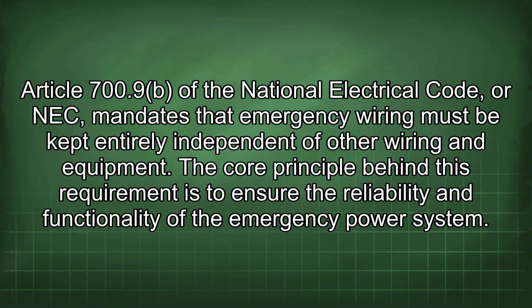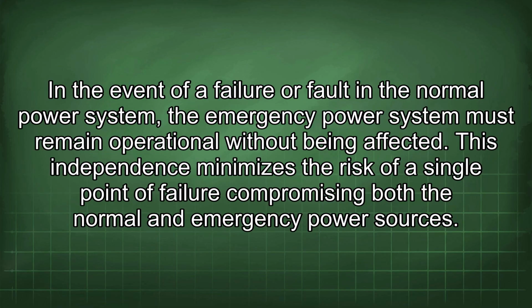Article 700.9 of the National Electrical Code, or NEC, mandates that emergency wiring must be kept entirely independent of other wiring and equipment. The core principle behind this requirement is to ensure the reliability and functionality of the emergency power system. In the event of a failure or fault in a normal power system, the emergency power system must remain operational without being affected.